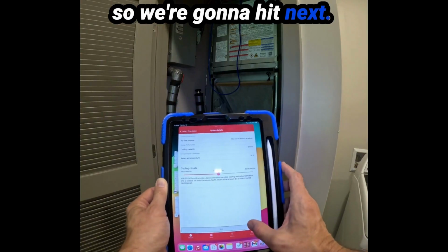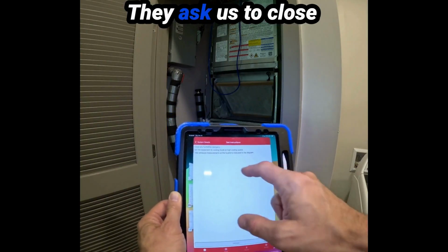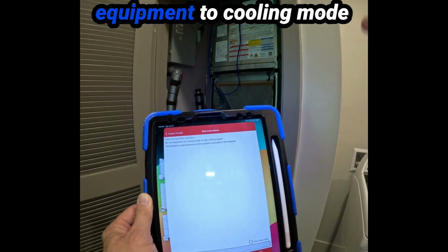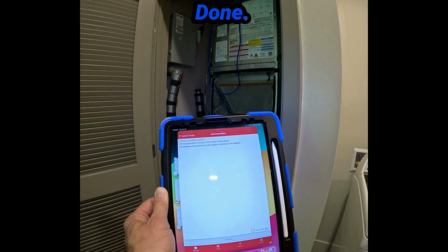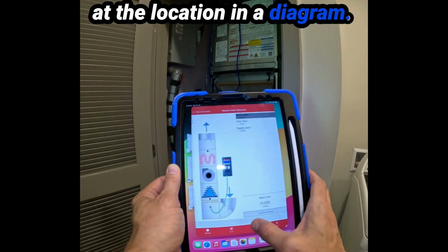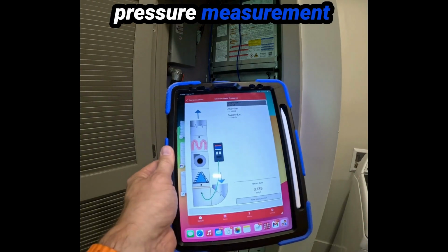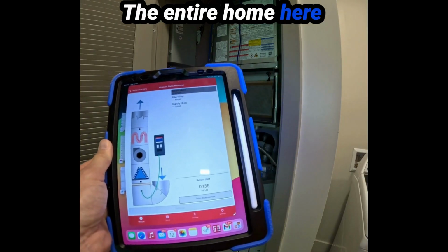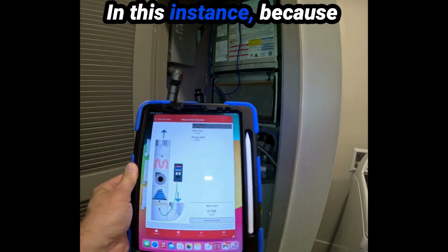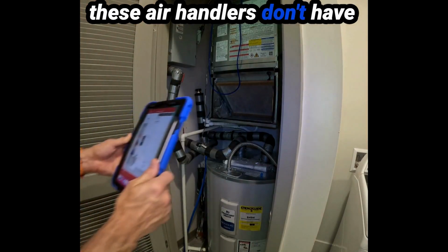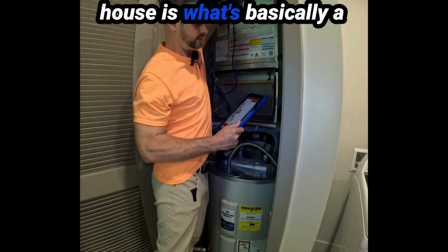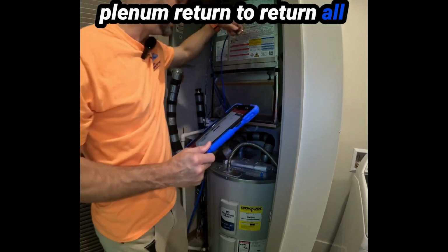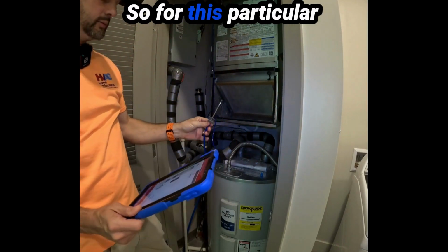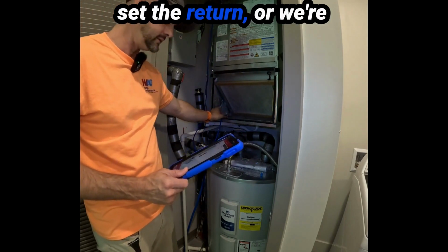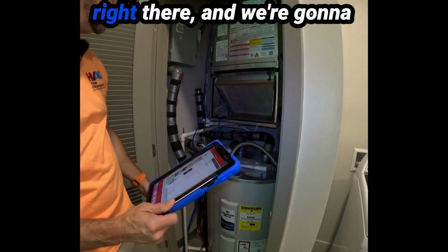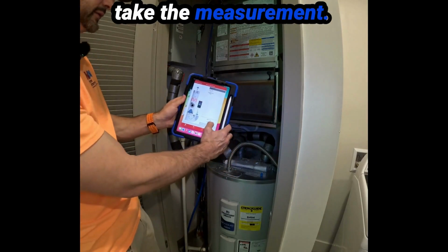So we're going to hit next. They ask us to close any humidifier dampers, done. Set equipment to cooling mode at high speed cooling, done. Take pressure measurement at the location in the diagram. So our very first pressure measurement is in the return duct. The entire home here is the return duct in this instance, because these air handlers don't have ducted return. They use the house as basically a plenum return to return all the air back to the air handler. So for this particular measurement, we're going to set the static probe right there, and we're going to take the measurement.